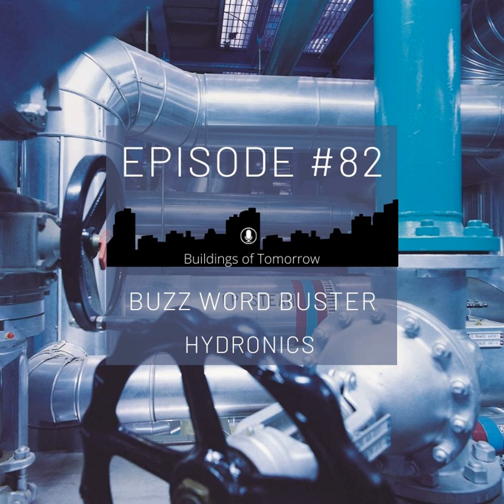And when I said before that we now have some preferred hydronic circuits and we want to run variable flow, of course this only became possible once variable speed pumps or variable speed drives for bigger pumps became available, and became also available at reasonable cost to be put into place. But today I would say it is standard even in areas where you want to run constant volume flow. Today you probably have a variable speed pump that you then just set to a constant speed because it's much easier to buy such a pump than another one.